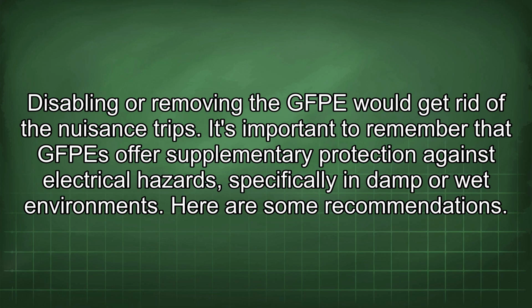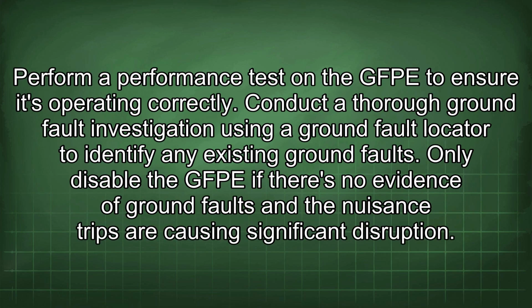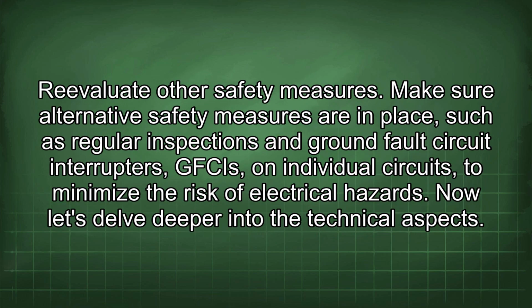Here are some recommendations. Perform a performance test on the GFPE to ensure it's operating correctly. Conduct a thorough ground fault investigation using a ground fault locator to identify any existing ground faults. Only disable the GFPE if there's no evidence of ground faults and the nuisance trips are causing significant disruption. Reevaluate other safety measures. Make sure alternative safety measures are in place, such as regular inspections and ground fault circuit interrupters, GFCIs, on individual circuits, to minimize the risk of electrical hazards.